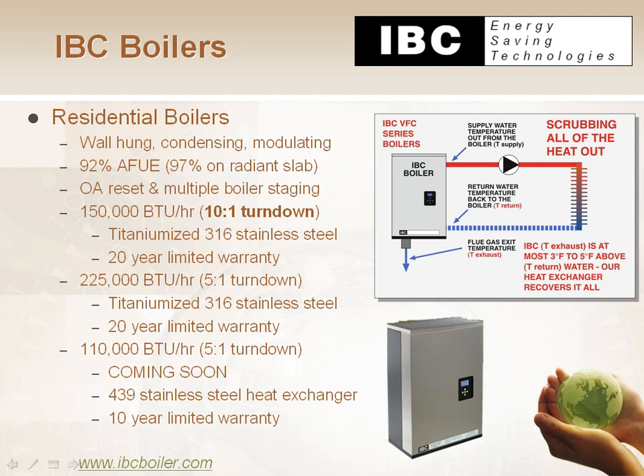The other thing that he does that's pretty cool is he can handle up to 3 different temperature loads. So I showed you an example before of 2 temperature loads. One of them was for space heating, where pump 1 was supplying to the space, and the other one was for the domestic hot water tank, where pump 2 was supplying. And I was able to switch between those 2 loads. The boiler could send water one way, or it could send water the other way, and change the temperature to match what that load needed. This boiler can do that with 3 different temperature load profiles.